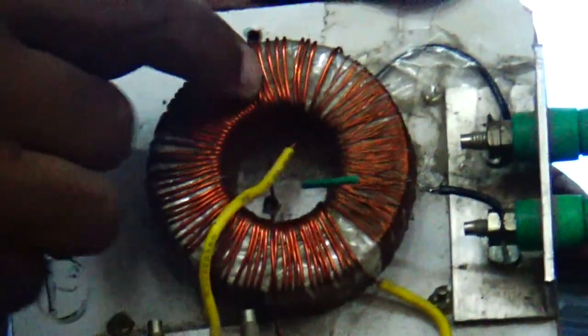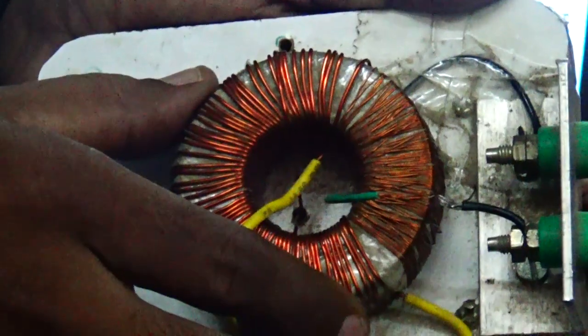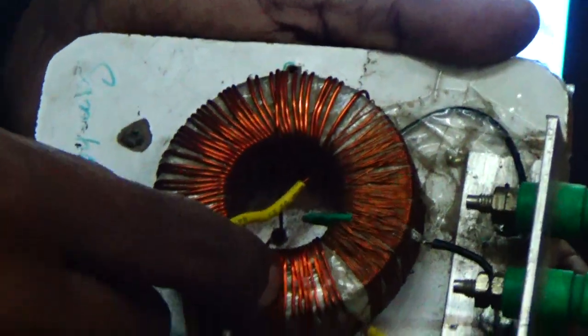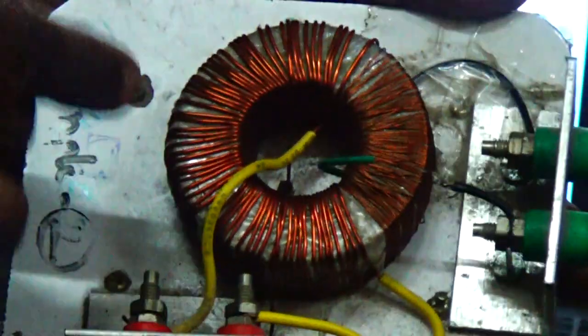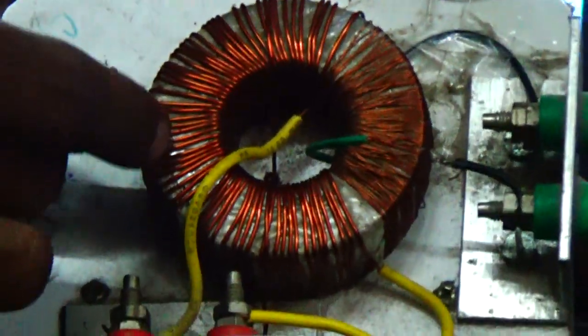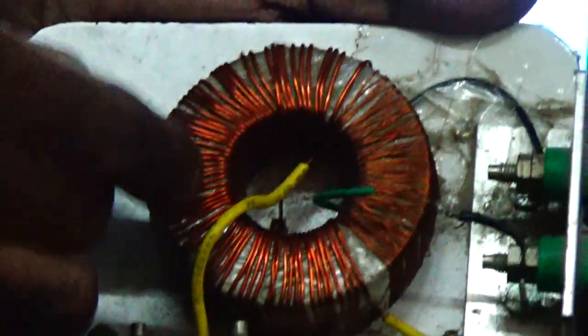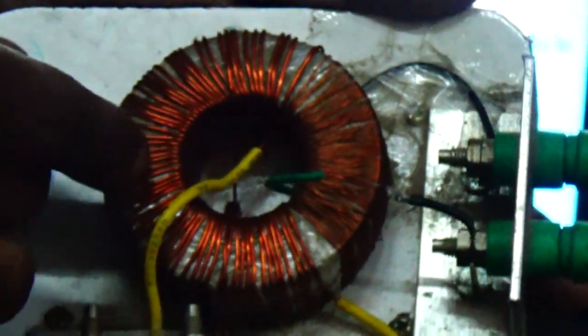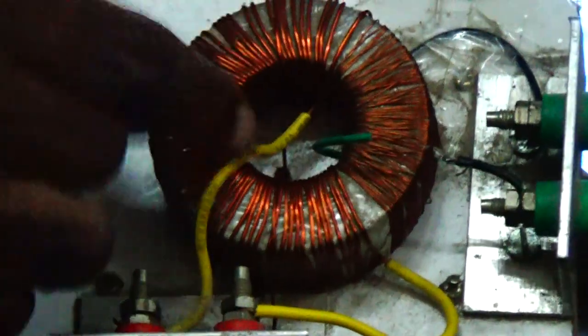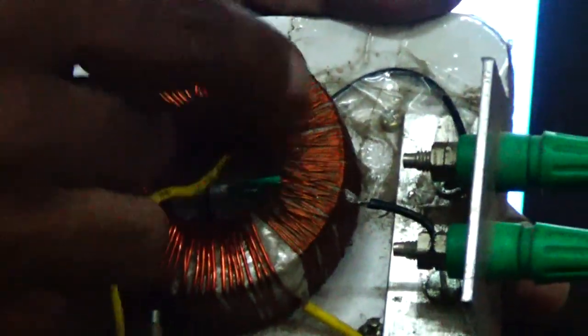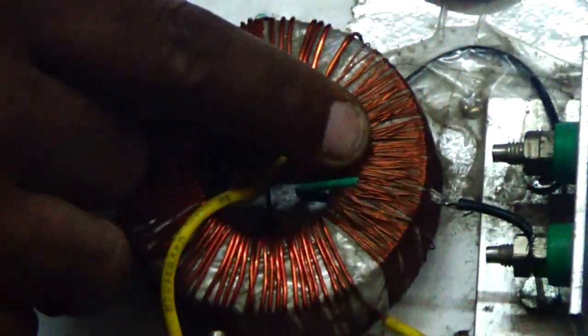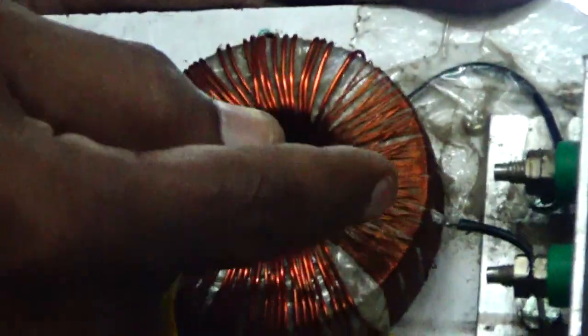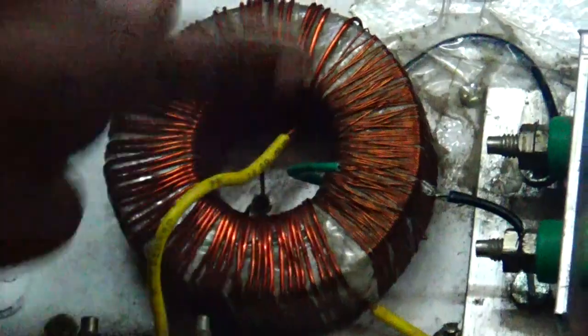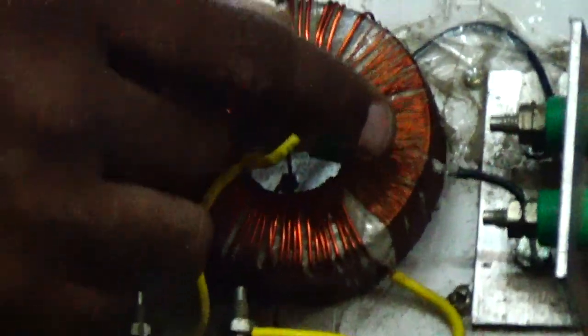is iron silicide, which is cast in the form of a toroid, on which we wind a primary coil consisting of a thicker gauge copper wire, and we have chosen this thicker gauge copper wire precisely so that we can pass reasonably high current without burning the coil. And on the same toroid sample, we wind a secondary coil using a thinner gauge copper wire, so that the number of turns in this coil can be increased, which will increase the signal or the induced EMF, thereby increasing the signal to noise ratio. So we use a thinner gauge copper wire to wind the secondary.